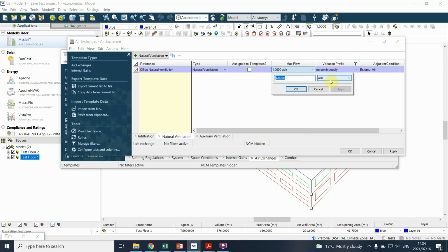In South Africa, you can look at the SANS 10400 section O, which gives general airflow rates, and I think these are often defined as liters per second per person. There's also definitions for air exchange rates per hour, and you must use the highest one in that case if you were to ever define it. But you can just use a basic.